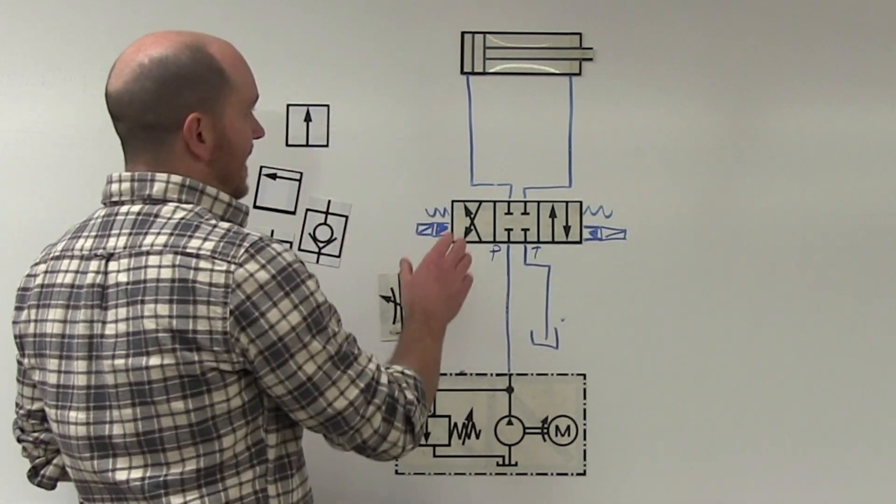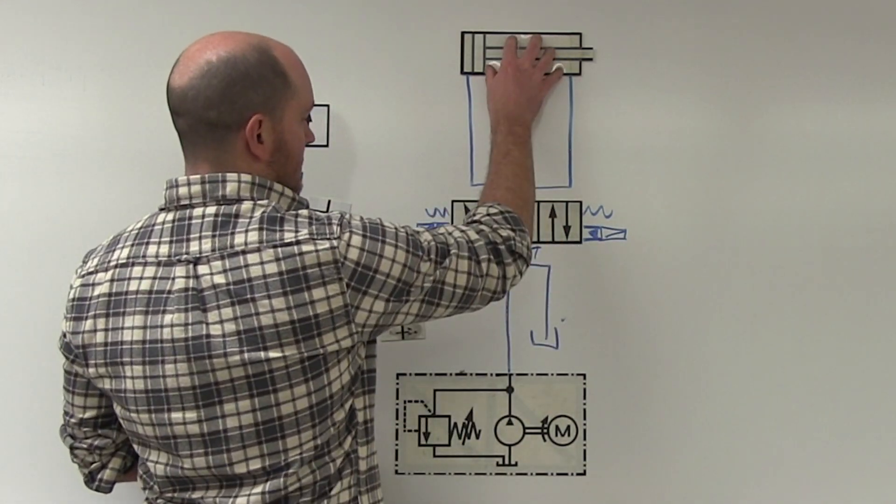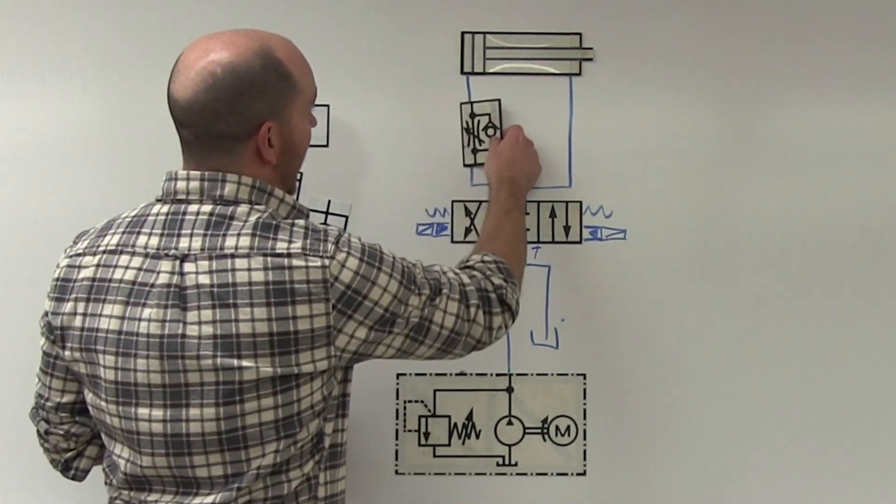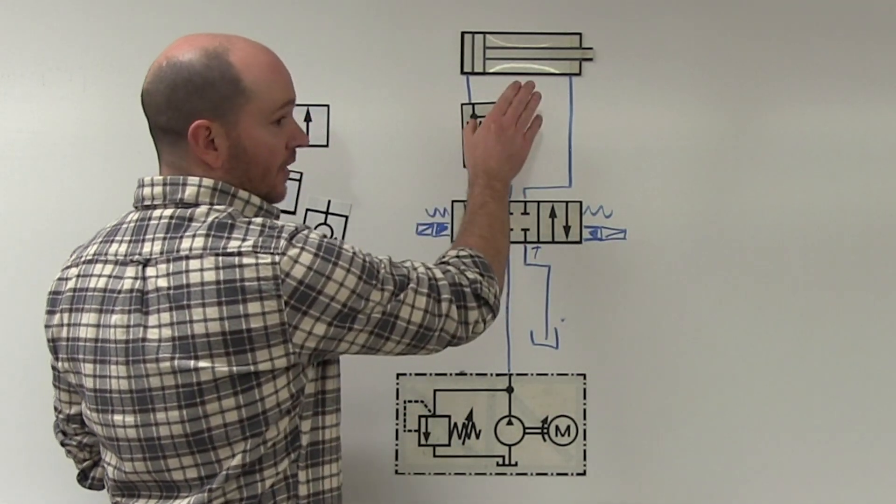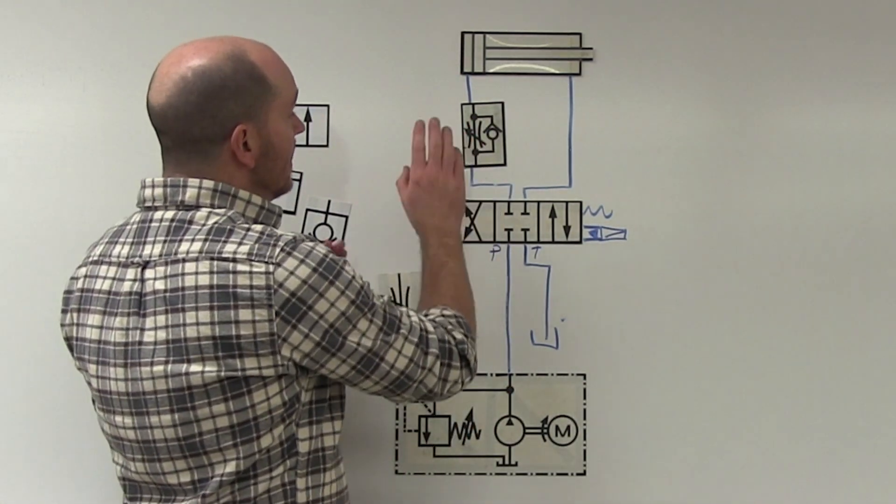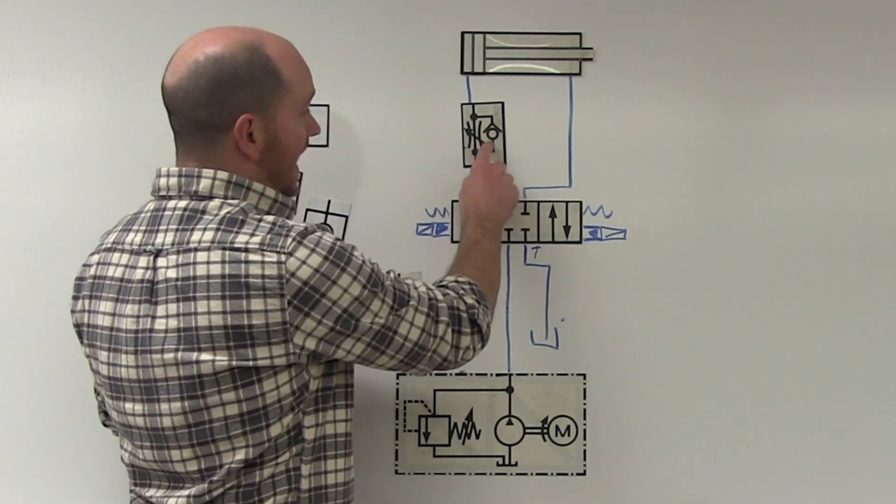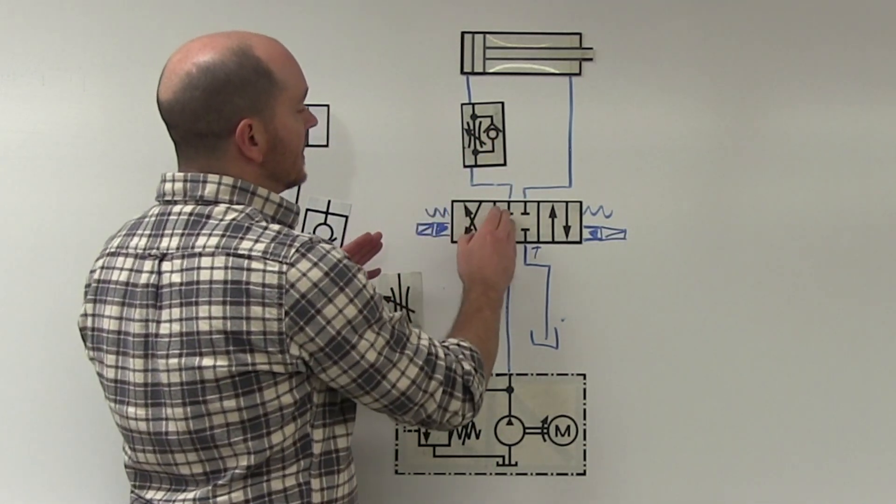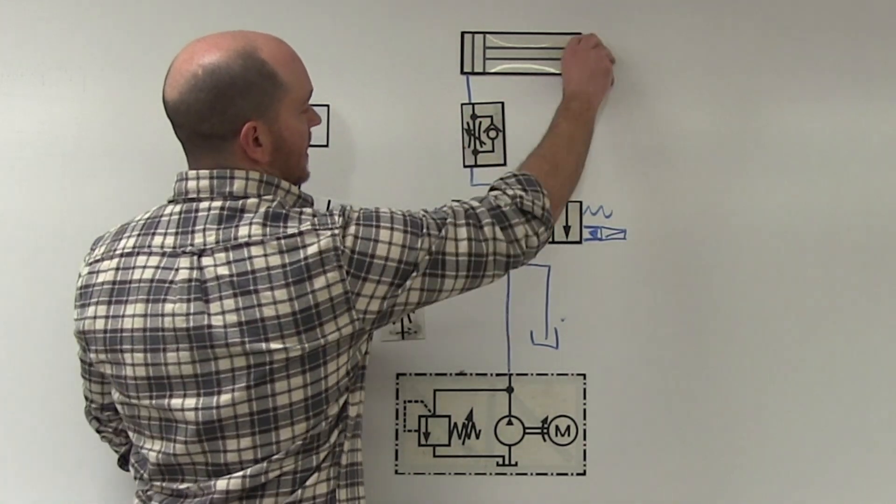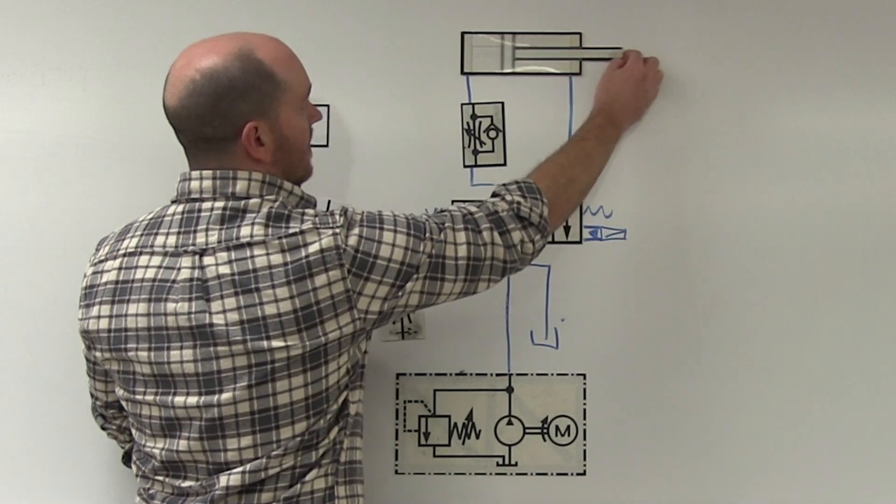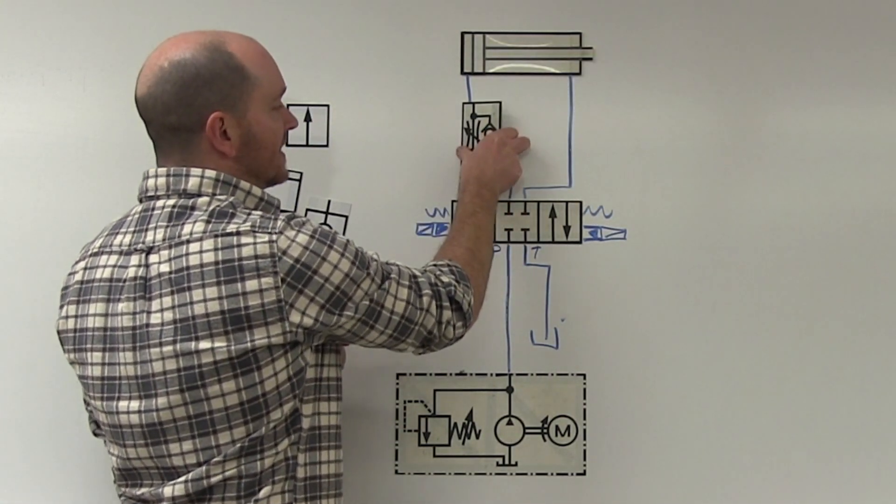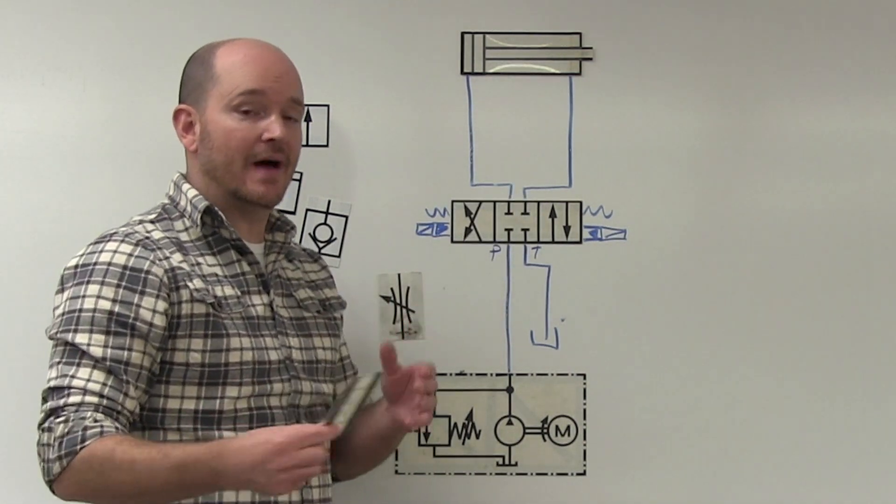But when do we need a bypass check valve after this? Well, I have a number of videos about how we actually meter in the flow, which I'll link at the end of this video. But you'll notice here that we need a bypass check valve for flow control, because we want to control the flow in only one direction. So oil will come up here, it will be restricted, but it will come back fast because it can go through the bypass check valve.